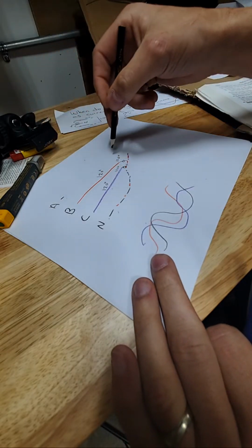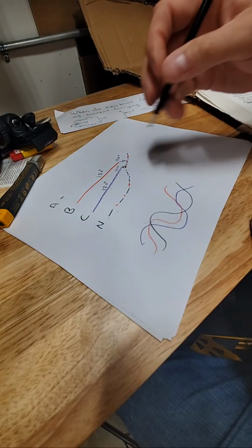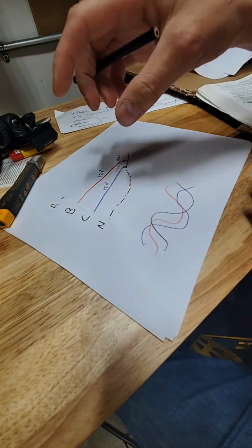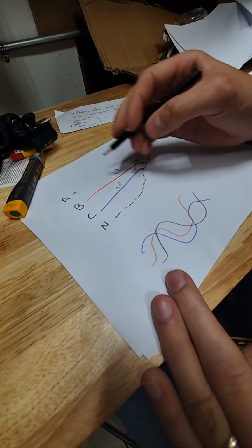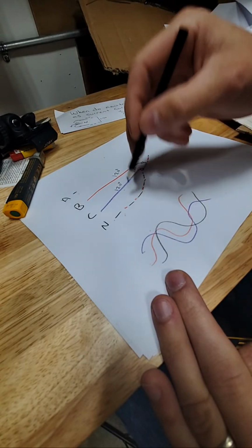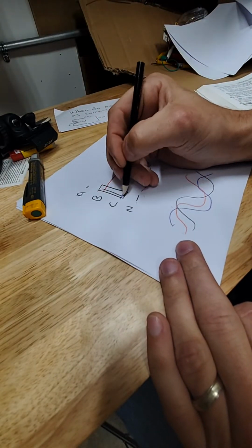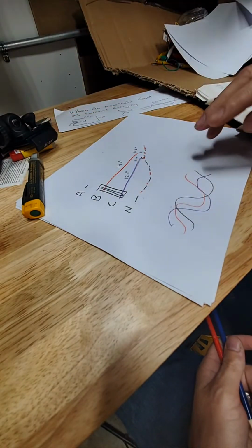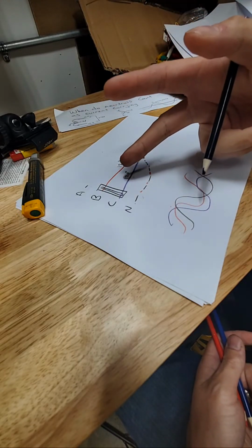If you had A here, this would all be in phase, and this neutral would cancel itself out because the current would be able to go back on each of them, and it would be a net of 0. But in this case, when you only take 2 of the hots and not all of the hots, you wind up putting current on your neutral when you take 2 of the phases. And yes, absolutely, this should be a double pole breaker. It's the same. Nothing's changed here. Got to be a double pole breaker. If you're using one neutral and you got multiple hots, you need a double pole breaker or a 3-pole breaker.